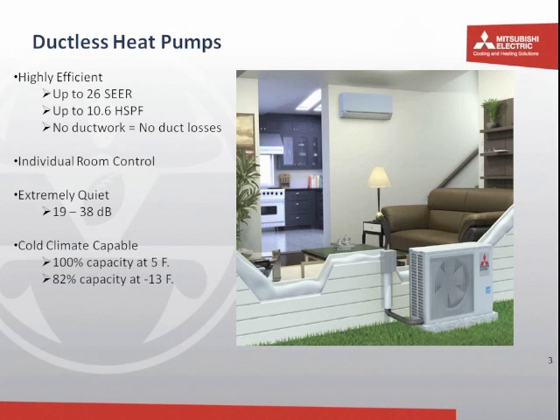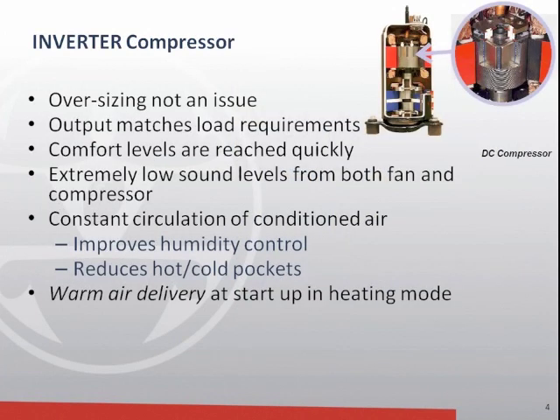The heart of the system is the inverter. And while not wanting to get super technical here, it is the black box inside that makes so many of the features available to us. And I wanted to spend a little bit of time on this. A traditional heating and air conditioning system has basically 2 speeds, on or off. And when it's on, it's operating at 100% of its nominal capacity. Occasionally, you'll run into a very efficient conventional system that's got 2 speeds, but typically that's as good as you're going to do. And if you can make the analogy to your car, if all you had was full throttle and 0 throttle, your ride would be pretty bumpy and your efficiency would be pretty low. Additionally, you'd have very great stresses on your mechanical components, which would be life limiting.